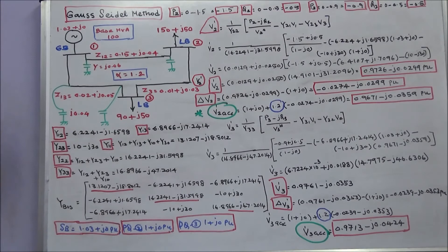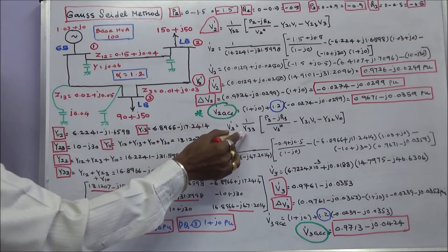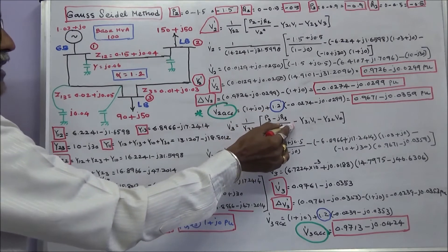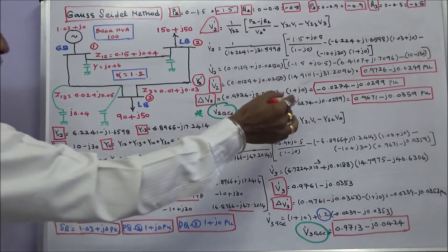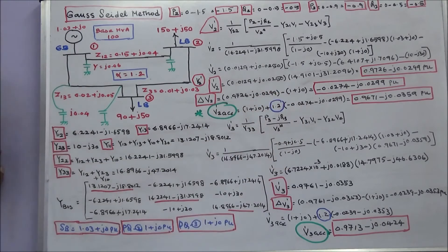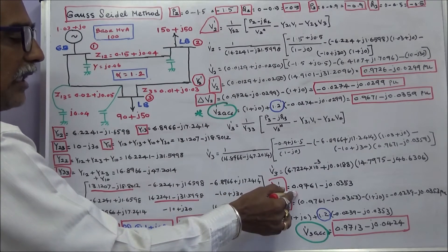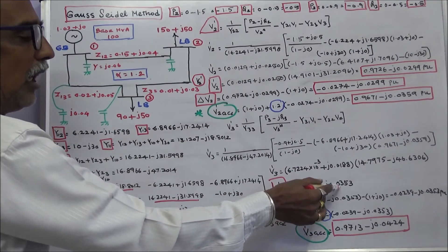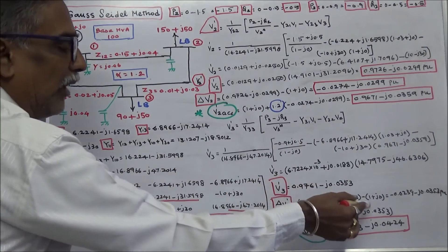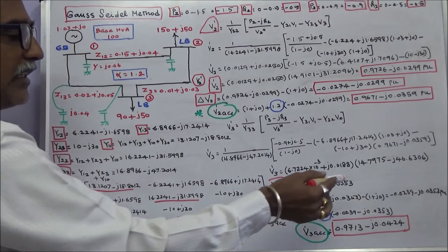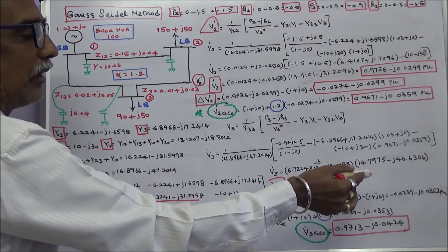Similarly, for V3: (1/Y33) × [(P3 minus jQ3) / V3* − Y31×V1 − Y32×V2]. Substituting all values, the first iteration V3 = 0.9761 minus j0.0353 per unit. The difference (calculated minus assumed) is minus 0.0239 minus j0.0353 per unit.